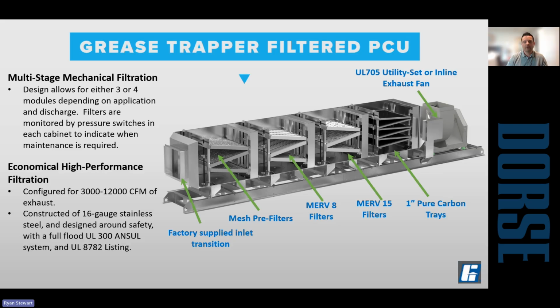I'm going to ask questions about what the discharge is like. Are we discharging into an alley? Are we discharging near residential condos, operable windows? And then we're going to figure out how much filtration do we need. So it can be configured with 3 or 4 modules. We can configure filters for each module based on the application. And then the final stage of it is going to be a carbon tray to absorb the remaining odors.